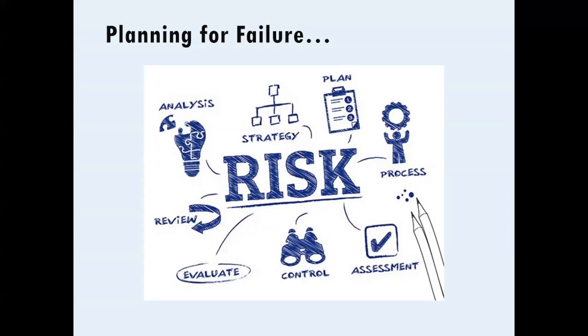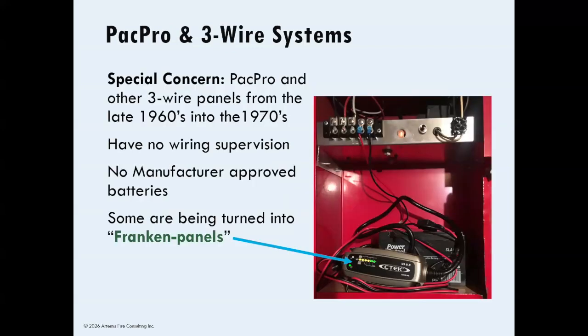If you're at this point where your service provider is simply keeping your system on life support with used parts, it is past time when you should be evaluating the risks and begin planning for your fire alarm upgrade. Of special concern are the PacPro and other three-wire panels from the 1970s. Short of when you are actively testing them, there is no guarantee that they are operating correctly.